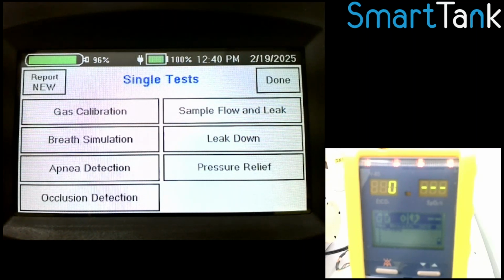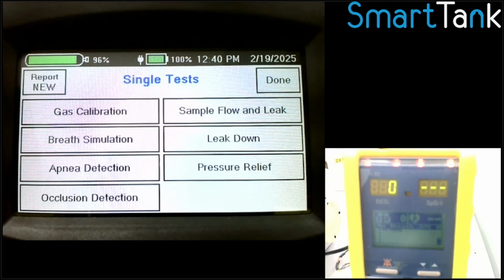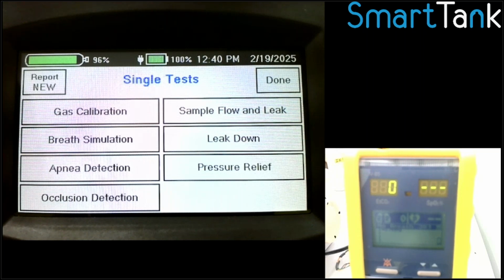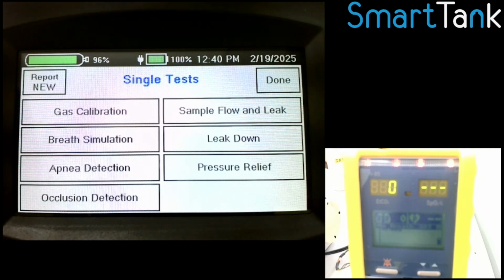In fact, we have test sequences for many of the patient monitors that are out there. And if not, we can write them. Essentially, you would still need your EKG tester, and if you're doing temperature testing, you'd need those devices to do the test, but the SmartTank will walk you through them and collect those results from you. And then when it gets to non-invasive blood pressure, it'll actually do that testing for you for the most part. And in the end, you get a test report of all your patient monitor testing. So we're trying to allow the SmartTank to do more testing than just CO2 modules. And again, if you say, hey, I want to test this device and use the sequences for that, and we don't have a sequence, we'll write it for you.